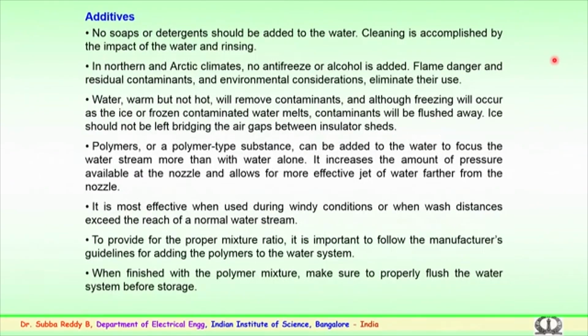The next topic is the additives for the water. What are the various additives being used for the cleaning of insulators? Water quality and resistivity we have discussed. As for additives, no soaps or detergents should be added to the water. This is a point to be considered. The soap solution or detergents used for cleaning will leave deposits on the surface if not properly washed. So, soaps or detergents should never be used for cleaning.